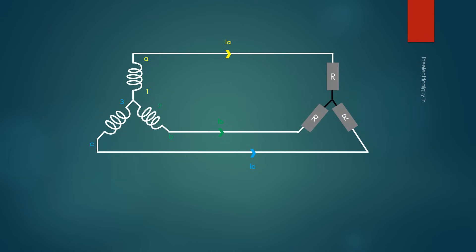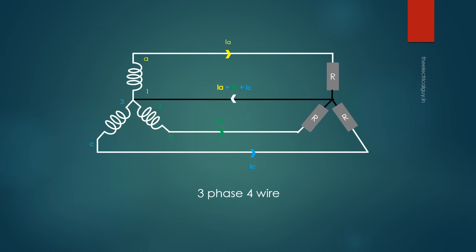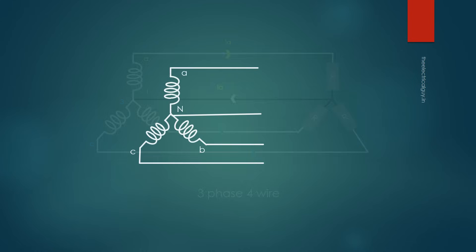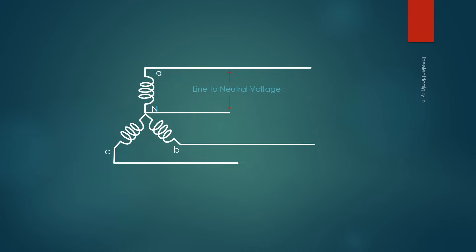The circuit with three wires is called a 3-phase 3-wire system, and the generator and load are said to be connected in Y or star. The circuit with a neutral is called a 3-phase 4-wire system, and is widely used to supply power to commercial and industrial customers. When discussing a star-connected 3-phase system, there are two key concepts: line-to-line voltage and line-to-neutral voltage. The relationship between these voltages and currents changes with the type of connection.